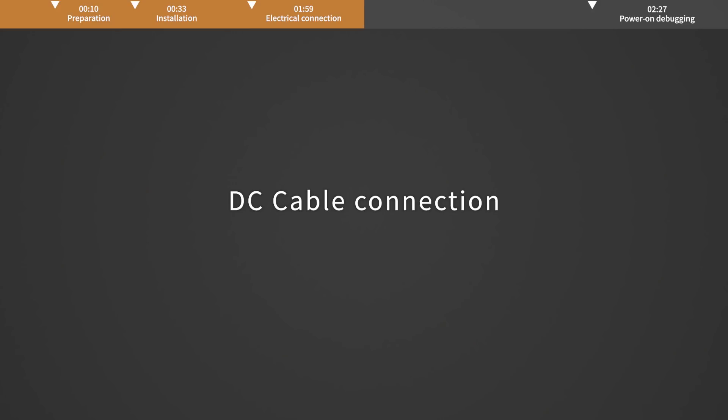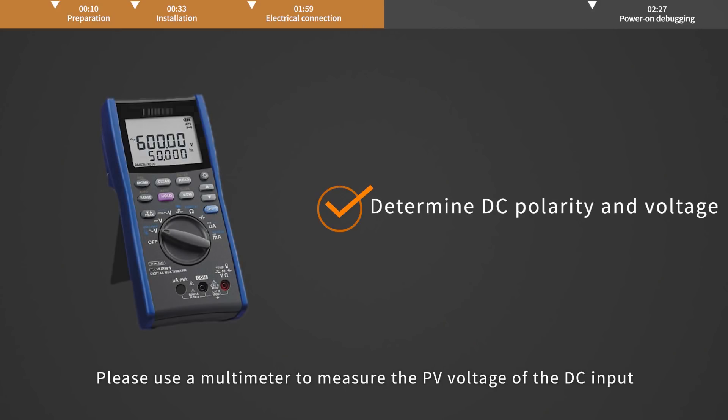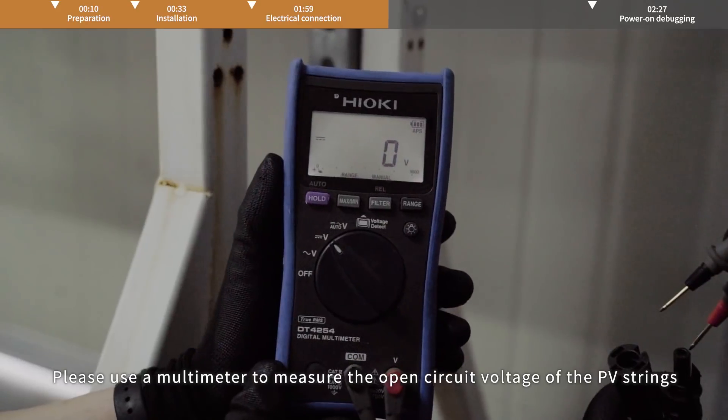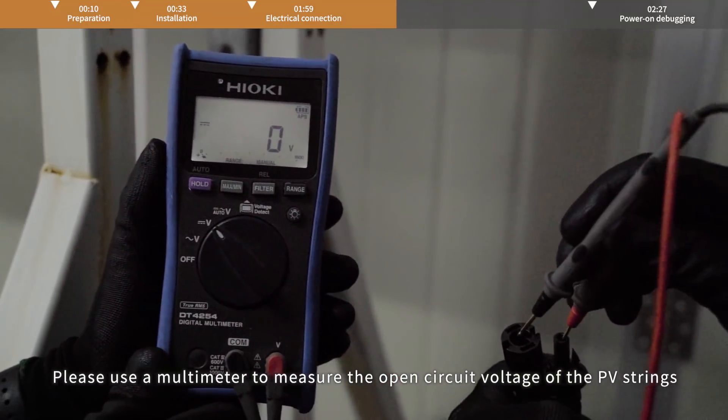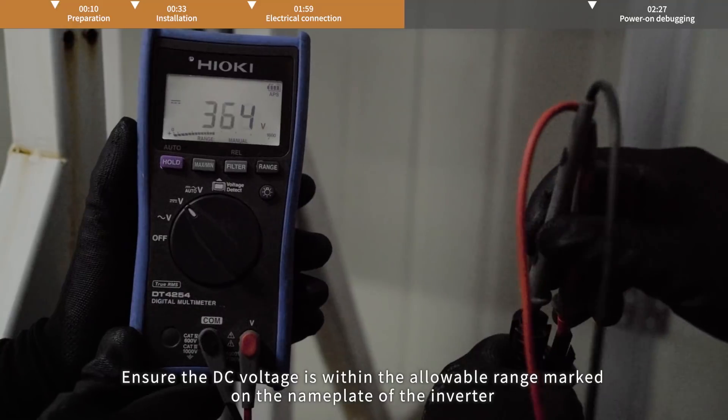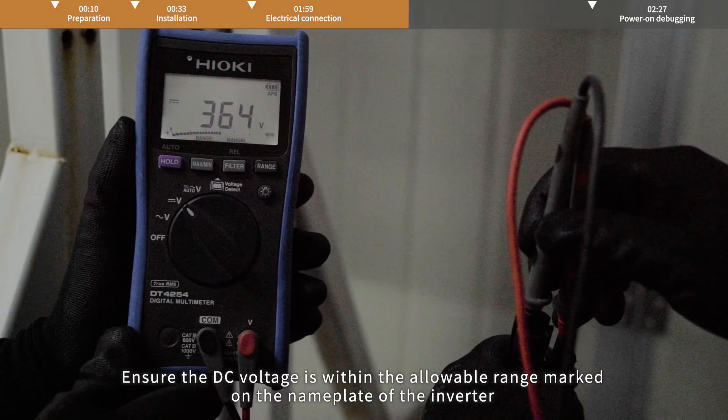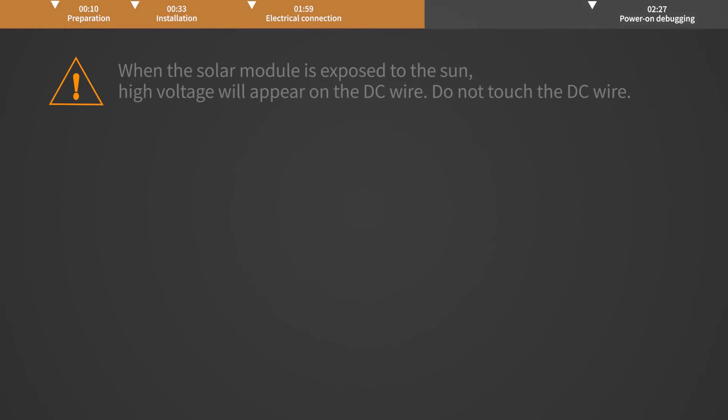DC cable connection. Please use a multimeter to measure the PV voltage of the DC input. Distinguish the positive and negative poles. Ensure the DC voltage is within the allowable range marked on the nameplate of the inverter.